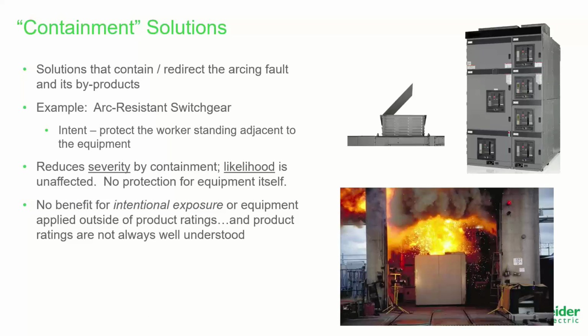Product ratings, you may not get protection for equipment applied outside of its ratings. That's true for any equipment, especially true of arc resistant equipment. And the main issue that I've seen with this, or area for misunderstanding, is understanding about the maximum arcing duration for low voltage arc resistant switchgear. Half a second is the typical value in the industry. If you've got a study done and EasyPower says you've got 60 calories at your main low voltage switchgear, guess what?